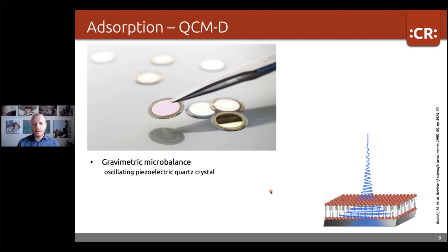If we then turn to QCM-D, it's not an optical technique. It's a microgravimetric, mechanical technique, so it's more analogous to sound waves. And the surfaces or substrates you use in this technique are actually the heart of the instrument.